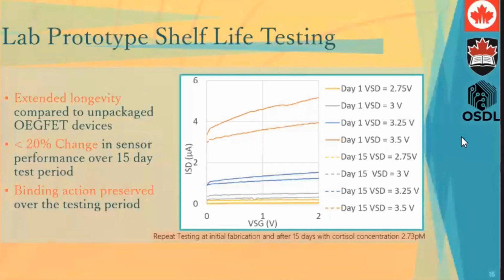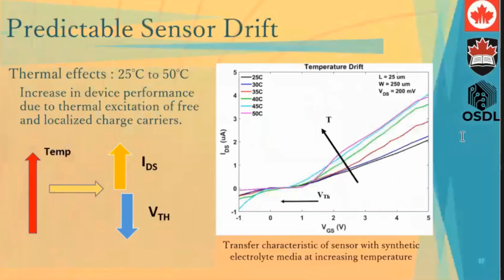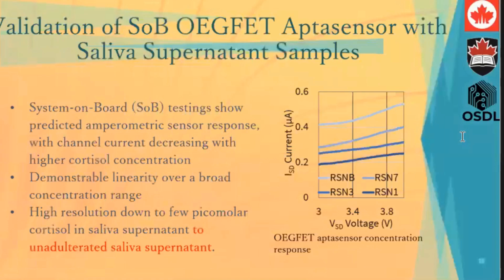The shelf life under use, so day 1, day 2, day 3 of the same chip, is only up to a few weeks right now, and we certainly hope to improve that. If you're going to go the continuous health monitoring way, it has to be a few months at least. We also see the predictable temperature drift, but we haven't done the full calibration yet. And the system on board analysis shows the amperometric response to concentration differences. We have tested the calibration, it works well.